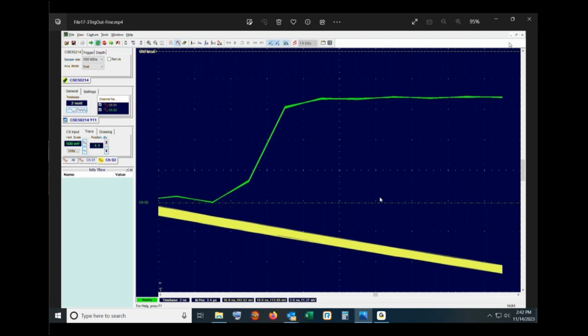So now I've gone down to 2 nanoseconds per division, and you can indeed see from the cragginess that a sample is the difference between these 2 sharp corners here. That's where the lines are connected, so those are the points. That proves basically that a sample is a division wide, but you can see that the width of the ribbon is way less than a sample. I'd say it's something like 1/20th of a sample.